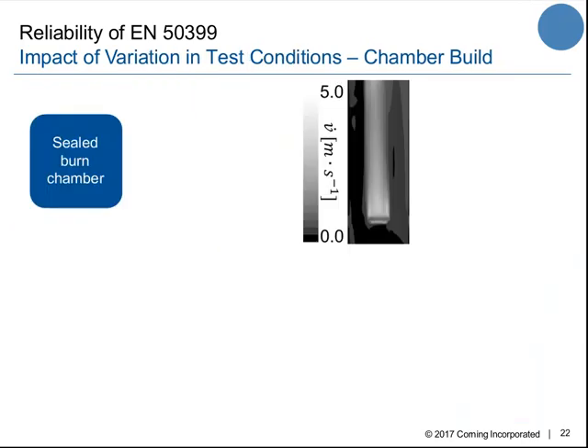The next point, how to, let's say, change air distribution in a chamber, is the sealing or leakages. So again, a CFD simulation of our chamber, but now you are standing in the door, looking in front of the burner into the chamber. So this is the burner, and this is the gas or air distribution in this chamber upwards in a high velocity regime. For a sealed burn chamber, what you see is that this is very homogeneous, very symmetric, and there's not so much happening around this gas stream.